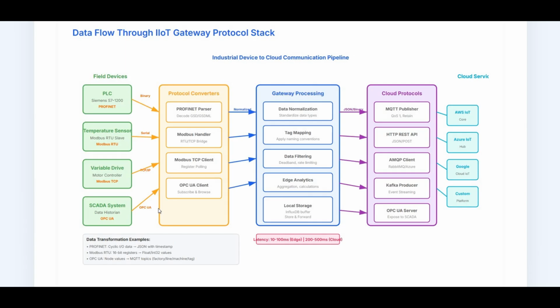Now, on the left, field devices generate data, right? A PLC like a Siemens S7-1200 speaks Profinet. A temperature sensor communicates over Modbus RTU, and a variable drive uses Modbus TCP, as SCADA systems expose data via OPC UA. Okay, and that raw data enters the protocol converter layer. A Profinet parser decodes GSD or GSDML files. A Modbus handler bridges RTU and TCP, and an OPC UA client subscribes and browses nodes. At this point, data is still device specific.